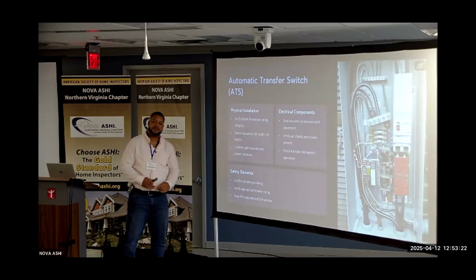So this particular grounding here has your neutral from the generator, the neutral from the utility, and the neutral going to the electrical panel. And instead of having your grounding electrode from your ground rods out in the earth going to the main panel, they're now coming to here, to your ground bar. And you're also going to have your cold water bond at this location as well. And as you see, all right, you see the green wire there. That's your bonding jumper, bonding the ground and the neutral together. So if you're coming out and inspecting and you do not see a bonding jumper anywhere, then there's a problem.